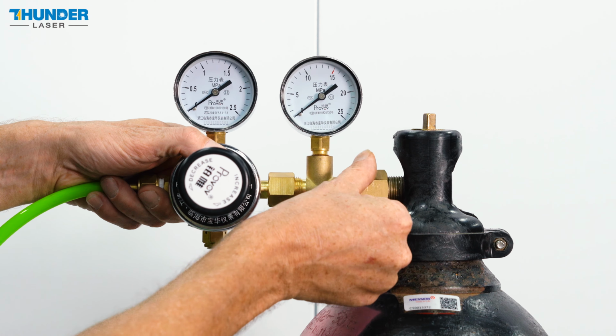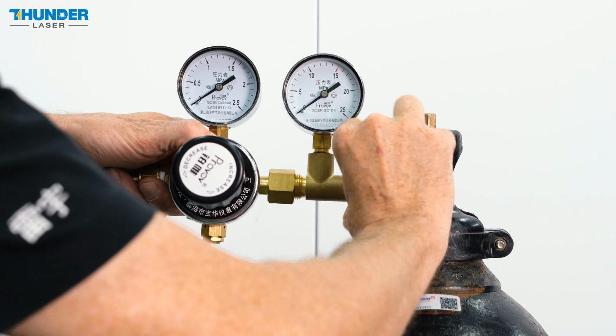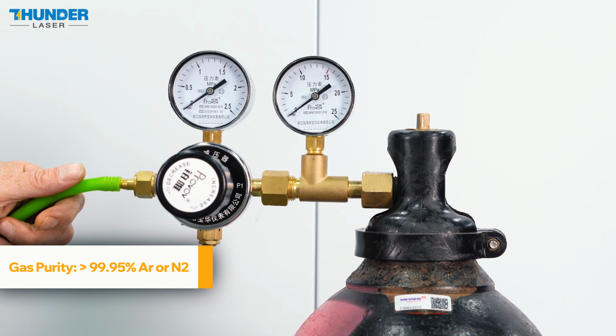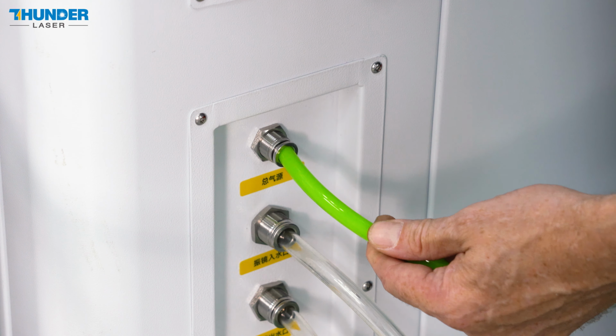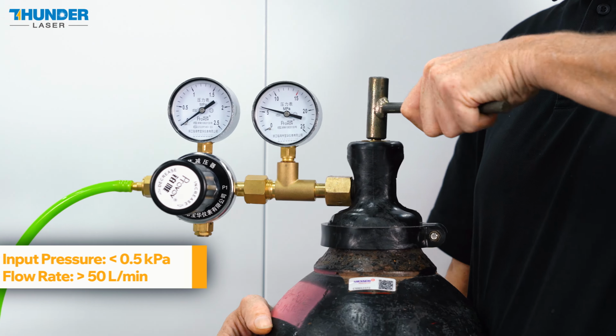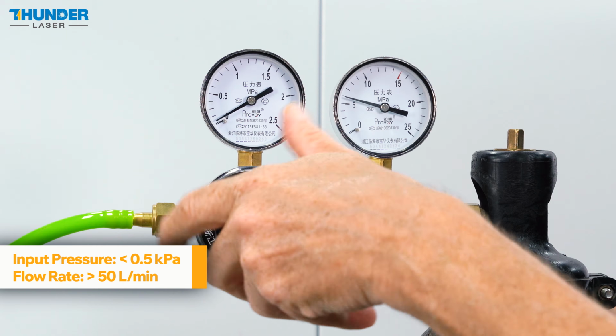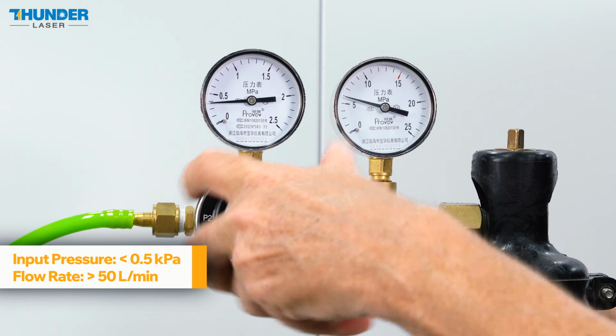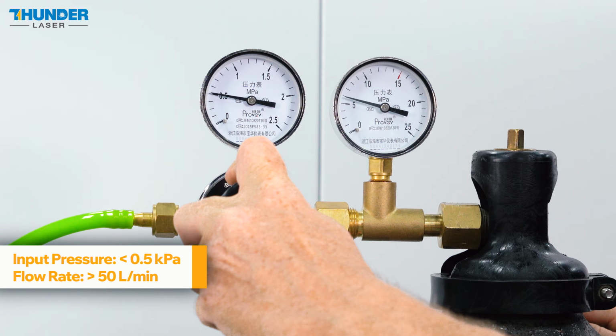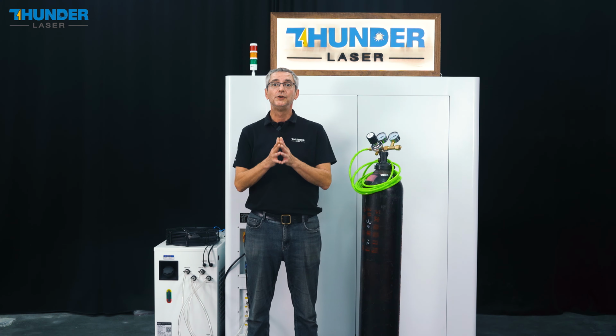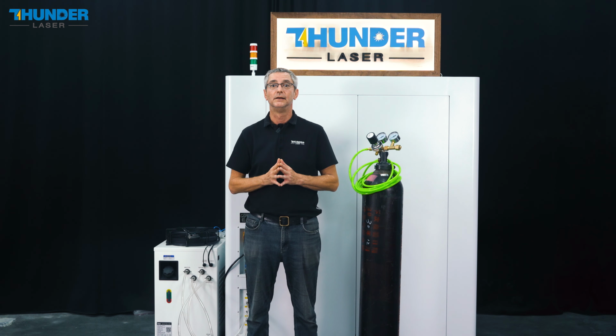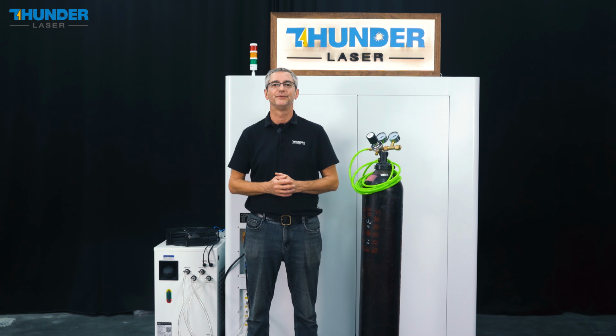Install the pressure reducing valve on your argon or nitrogen cylinder. The purity should be above 99.95%. Connect the 10 mm gas hose from the valve to the main gas inlet on your machine. Open the cylinder valve and confirm. The input pressure should be below 0.5 kilopascals and the flow rate above 50 liters per minute. Be careful, your print room must have an oxygen concentration alarm installed. The purging cycle will displace ambient air with inert gas.